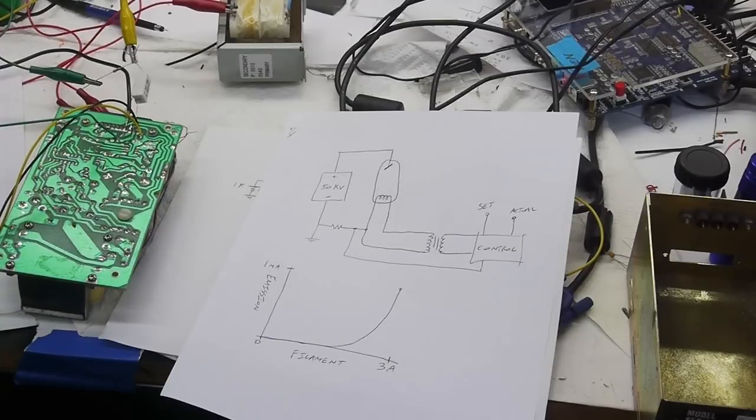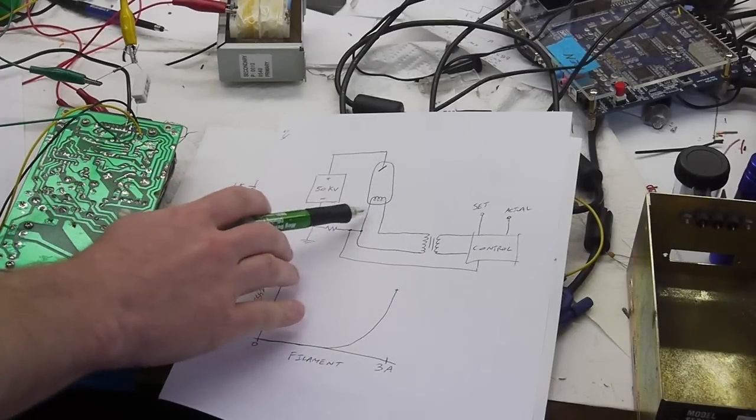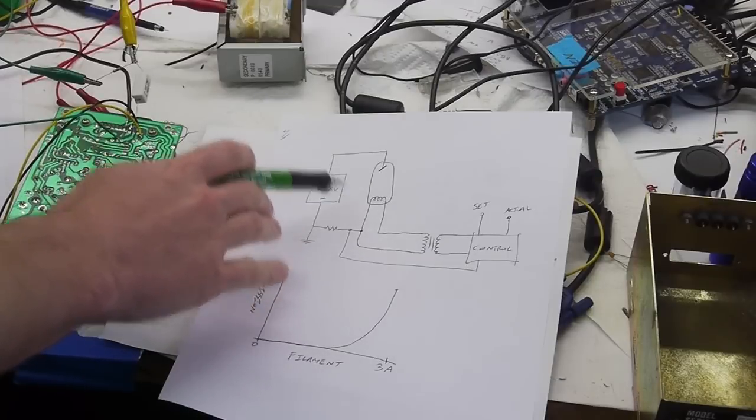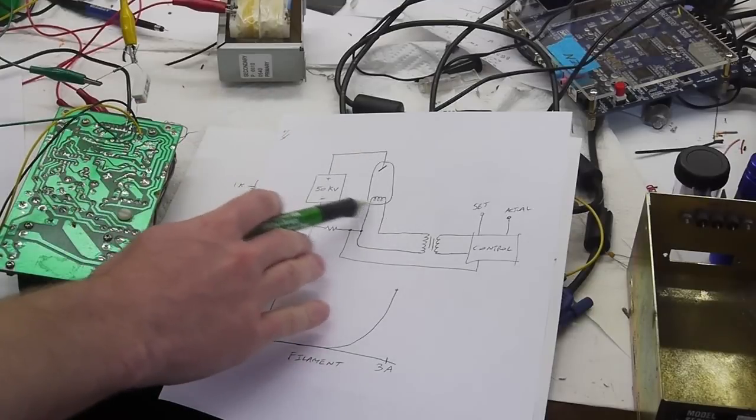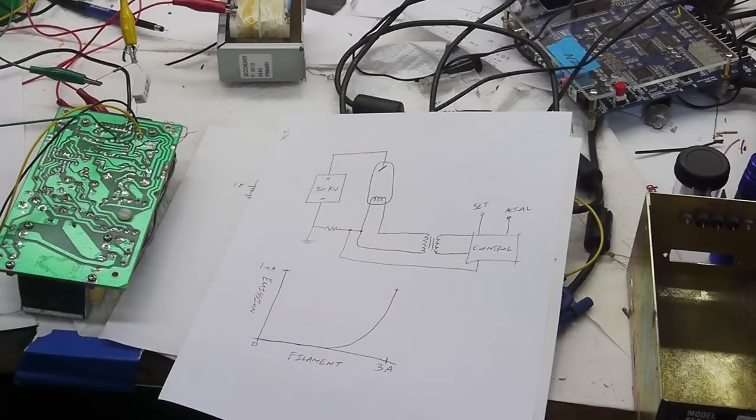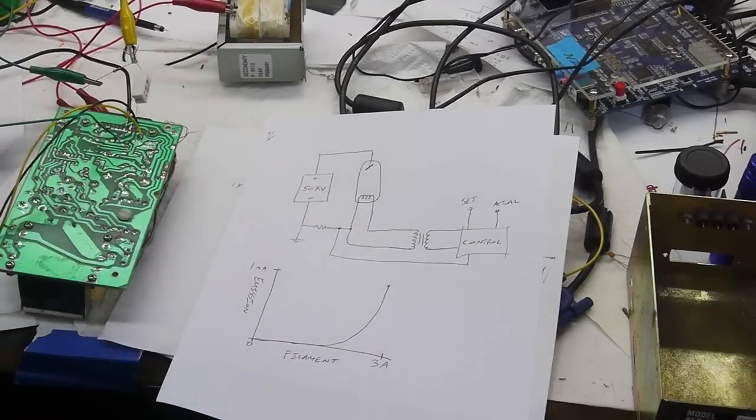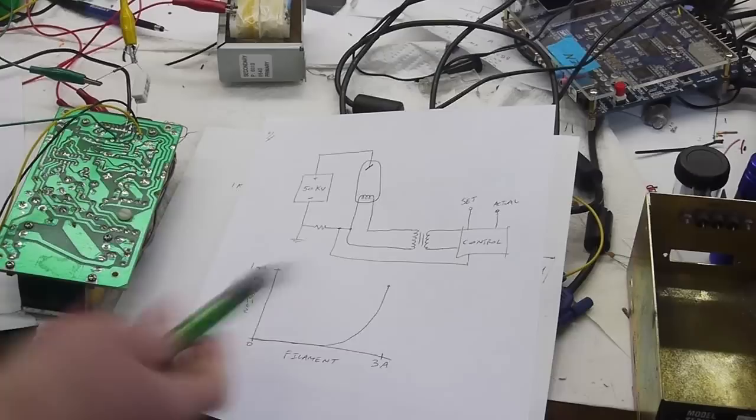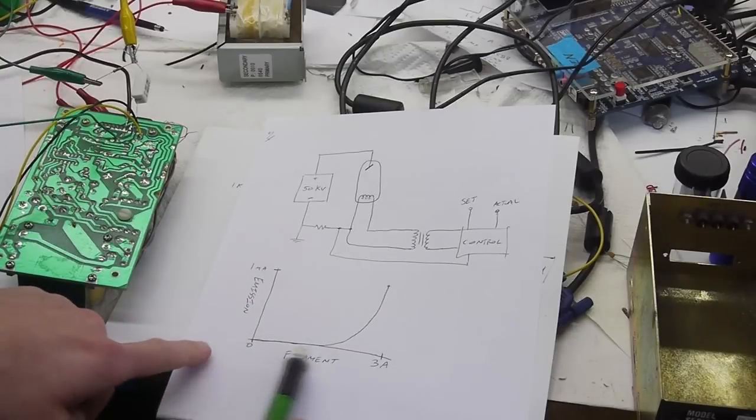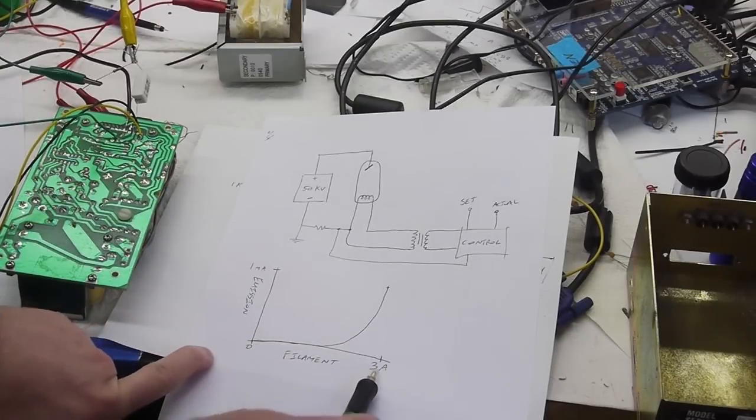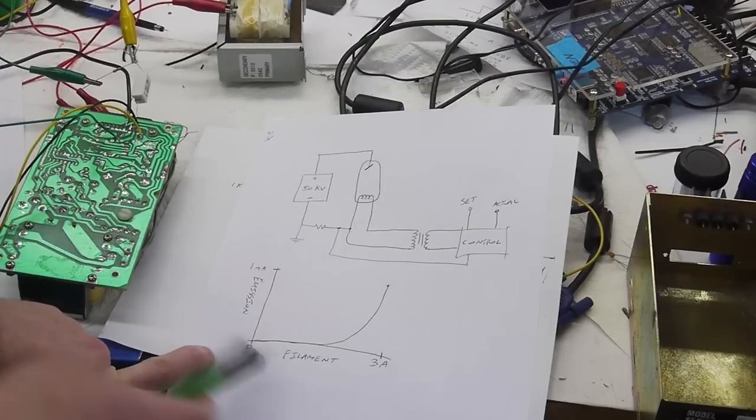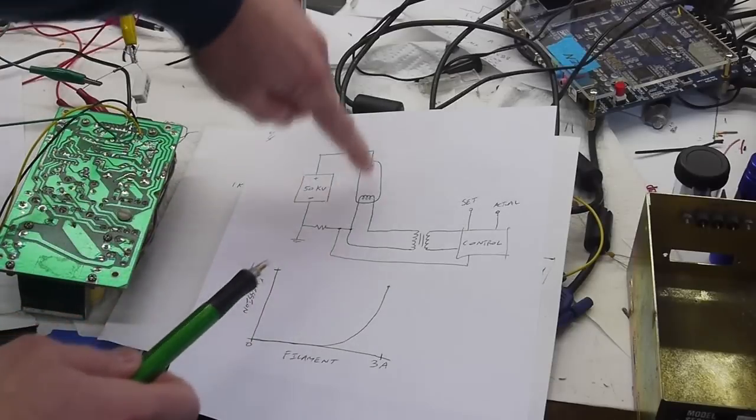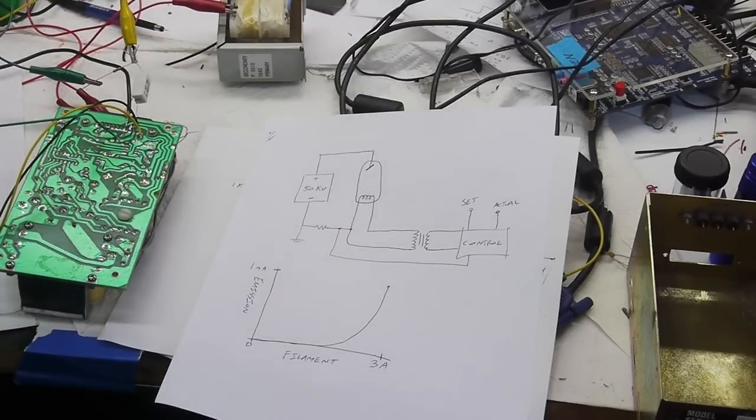But first I wanted to show you how an x-ray tube typically works. You've got an anode here and a filament here and you put a large DC voltage across these two and then you heat up the filament with typically a high current low voltage source. It's actually the temperature of the filament that regulates how much power the tube is going to consume and it's a nonlinear relationship. So as you heat up the filament, put more current through the tungsten piece of wire, it'll get hotter, you get more and more emission current which is the amount of current flowing through the high voltage supply.